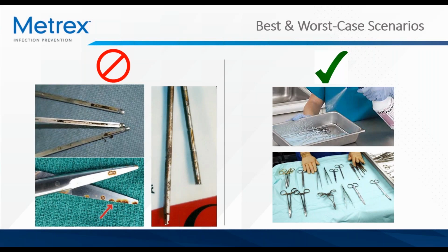We can take a look at some best and worst case scenarios here. On the left, you can see the impact of improper point of use pre-cleaning and the impact it's had on this instrumentation in the picture. Organic soil and bioburden were allowed to dry onto these instruments and started kind of eating away at these metal surfaces. You can see signs of pitting and corrosion.